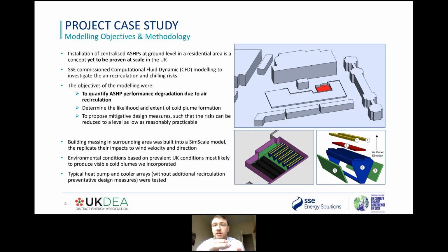So the building massing in the surrounding area was built into this CFD model to replicate the relative impacts of the geometry and massing of the buildings in the area with respect to breaking wind, or windbreaks, sorry, and the flow characteristics of the air through that area. The environmental conditions that were modelled were based on the UK conditions that were most likely to produce visible cold plumes. Our partner could explain this in a lot more detail, but it's due to the relative humidity and temperature conditions where cold plumes are likely to form. And this is typically around 1 to 2% of the year on an annualized basis, but it is a significant enough likelihood that we would need to investigate it and model on this worst case scenario.